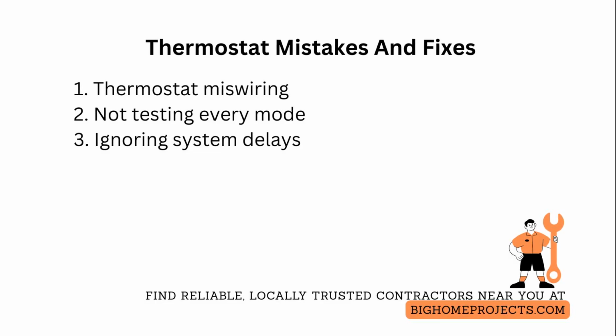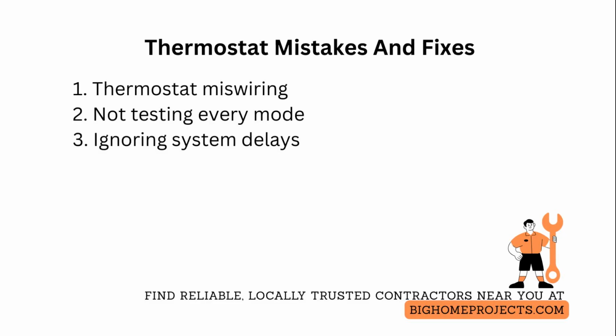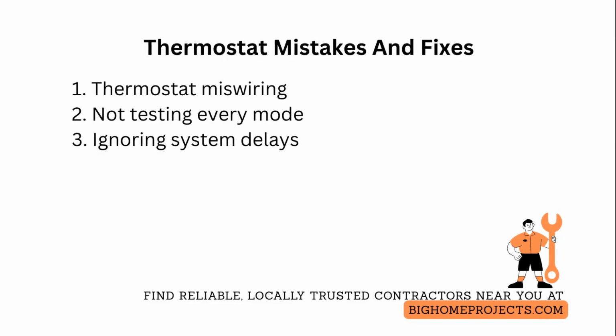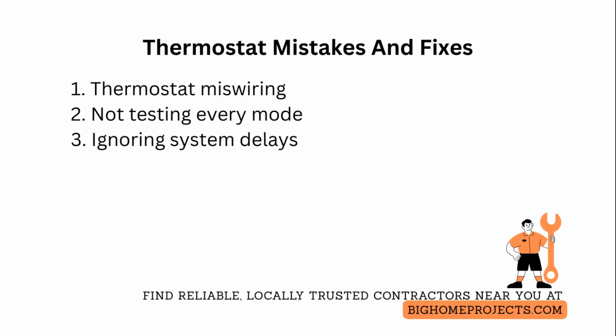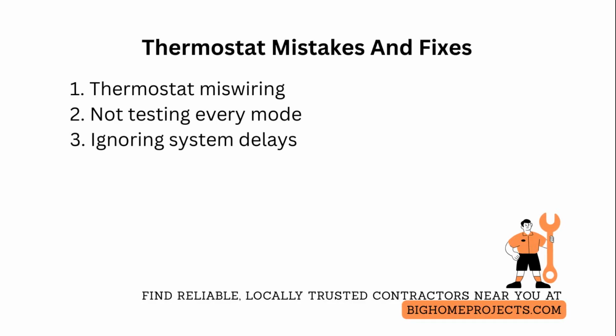One of the next frequent problems is failing to test every mode, which causes surprises when a rarely used mode is needed. Fix by systematically running heat, cool, fan, and any heat pump auxiliary functions and allowing manufacturer-specified delays so controls and safety interlocks can engage.